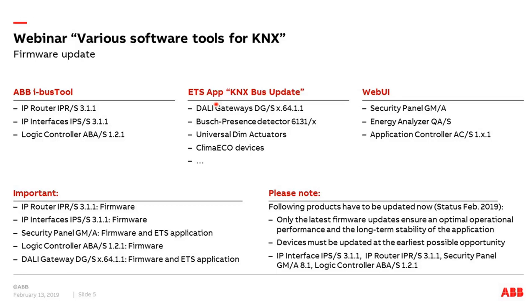The current situation as of February 2019 is that we have an important update available for four products: the IP router IPR/S 3.1.1, IP interface IPS/S 3.1.1, security panel GMA, and the logic controller ABA/S 1.2.1. There is an important firmware update necessary to ensure optimal operational performance and long-term stability. It's really a must to update these devices as early as possible.